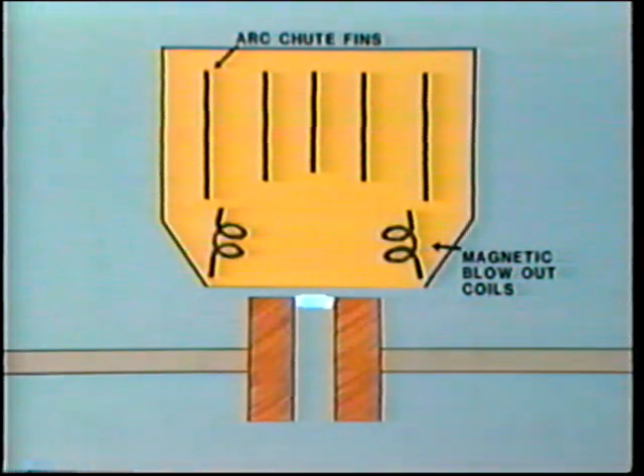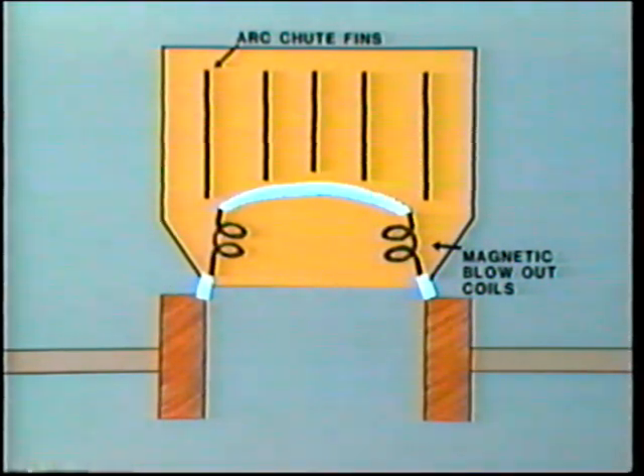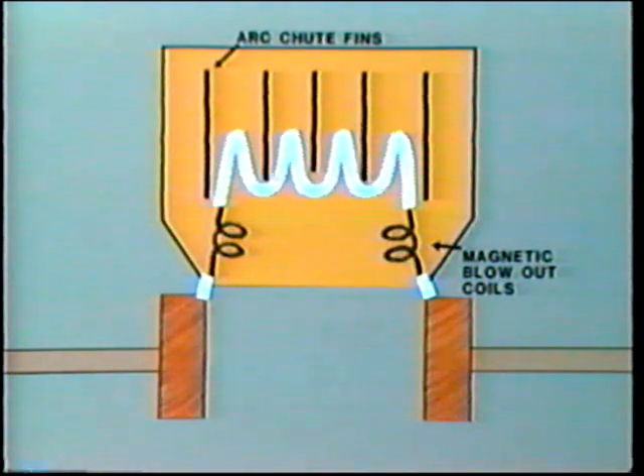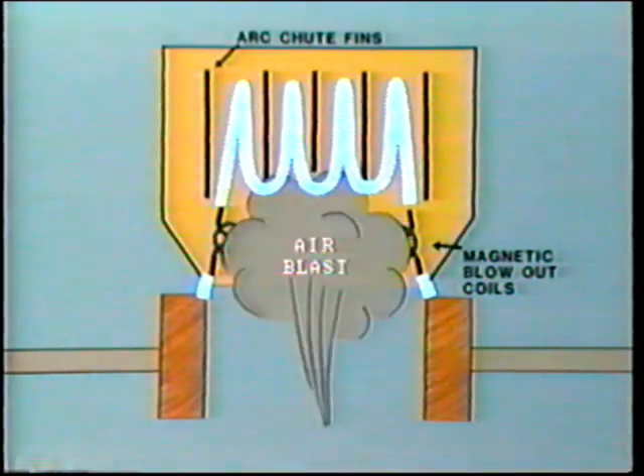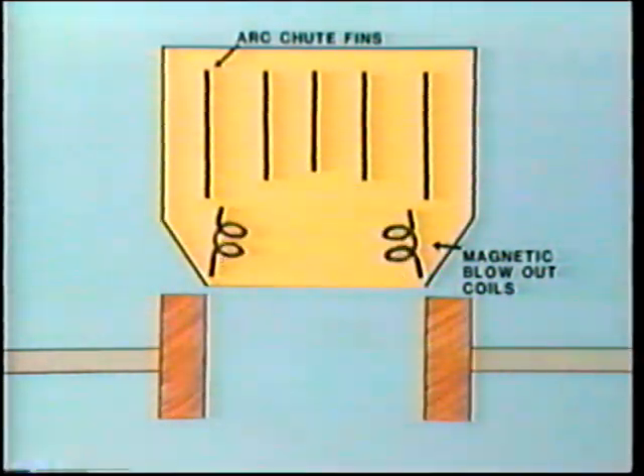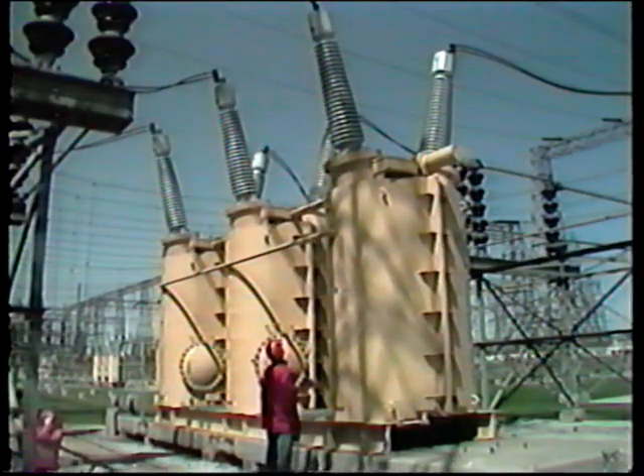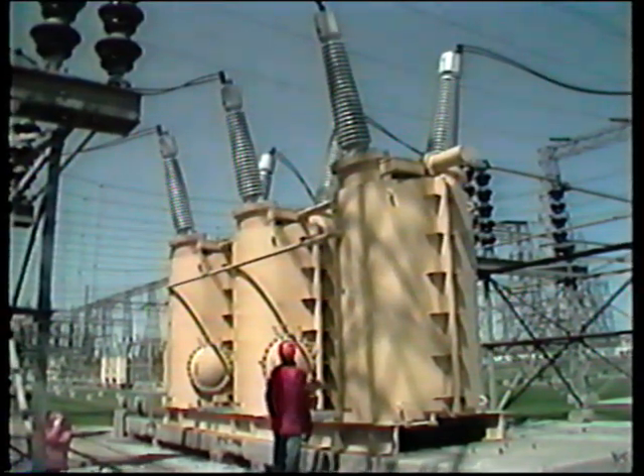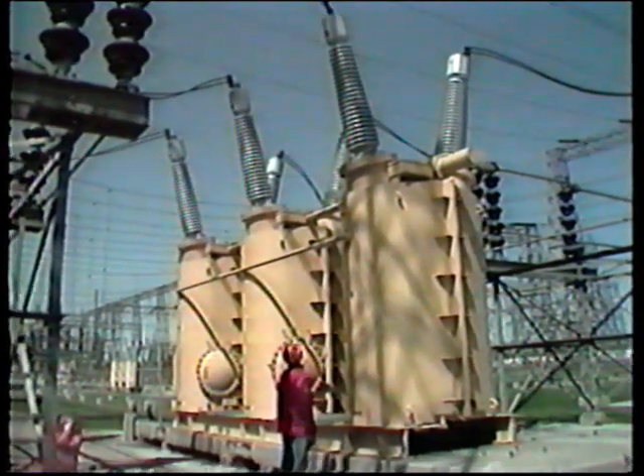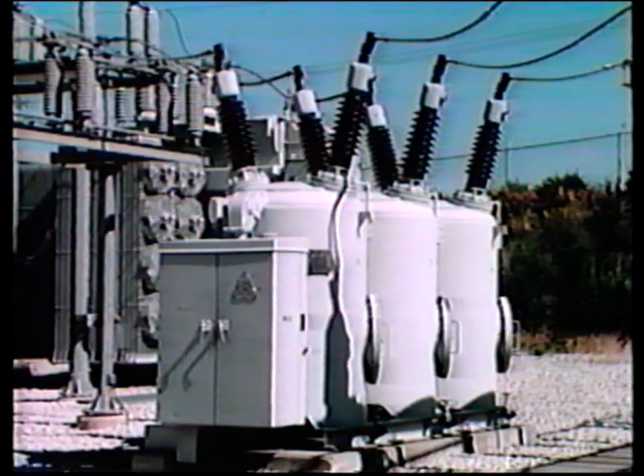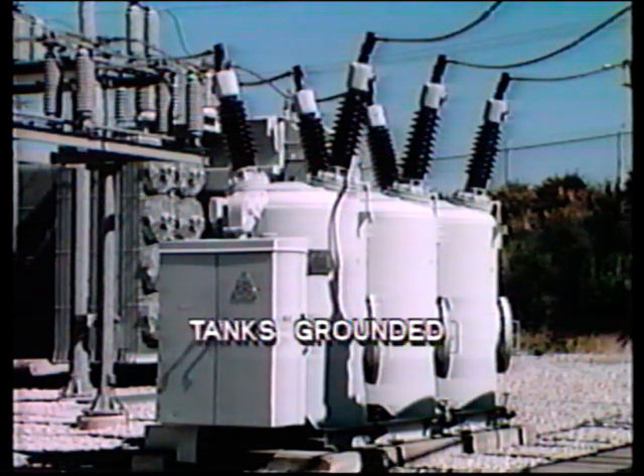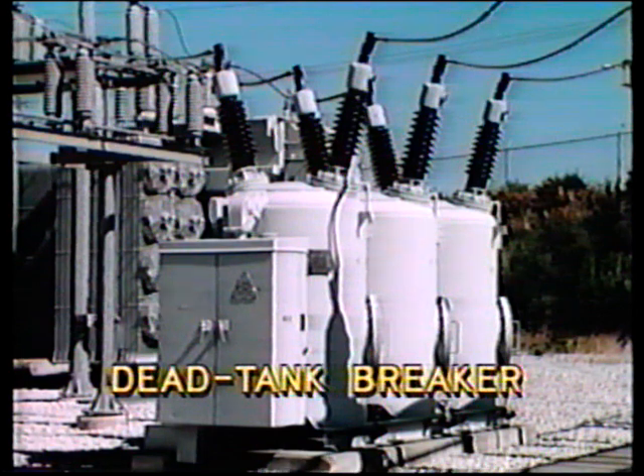As the contacts open inside the interrupter, an arc is drawn. It is essential that this arc be extinguished immediately and the contacts thoroughly insulated from each other so as to prevent a restrike, which could result in considerable damage to the breaker. Various methods are used to quench the arc inside the interrupter, depending upon the size and voltage of the breaker. The quenching medium may be oil, as in the case of this 132 kV oil circuit breaker. In this type of breaker, all 3 phases are immersed in oil tanks, and the tanks are grounded. This is known as a dead tank breaker. We mention it here because the item does have some significance in protection, as you'll see in later tapes.